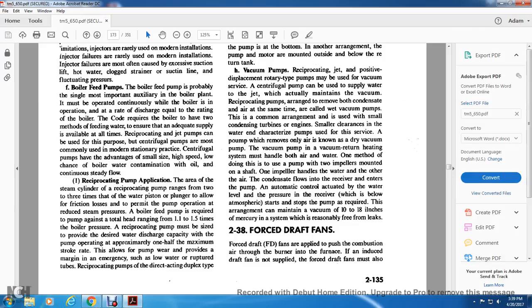Reciprocating pump application. The steam cylinder of a reciprocating pump ranges from two to three times the area of the water piston or plunger, to allow for friction loss and to permit pump operation at reduced steam pressure. The boiler feed pump is required to pump against a total head ranging from 1.1 to 1.5 times the boiler pressure. Reciprocating pumps must be sized to provide the desired water discharge capacity with the pump operating at approximately one half the maximum stroke rate. This allows for pump wear and provides a margin for emergency, such as a low water condition.